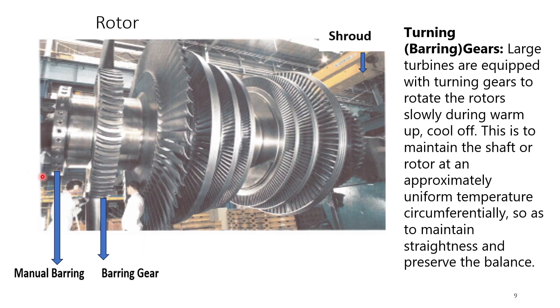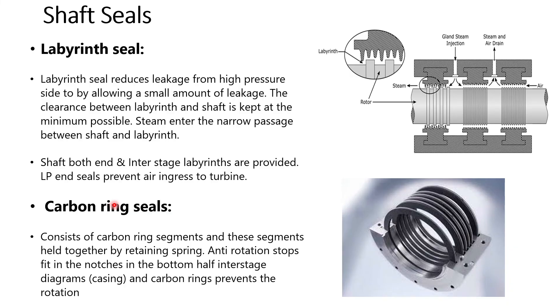The rotor is provided with a manual barring arrangement as well as a barring gear to rotate the turbine slowly during startup for uniform heating, and also when the turbine is shut down to cool it to a safe level. This is done to avoid bending of the shaft and to maintain the straightness of the shaft.